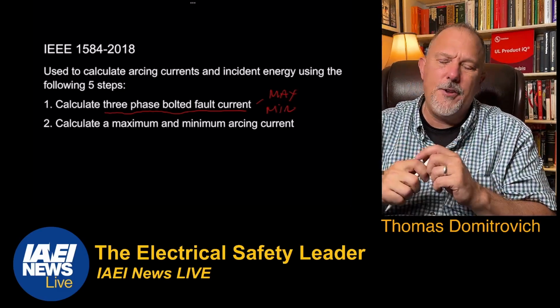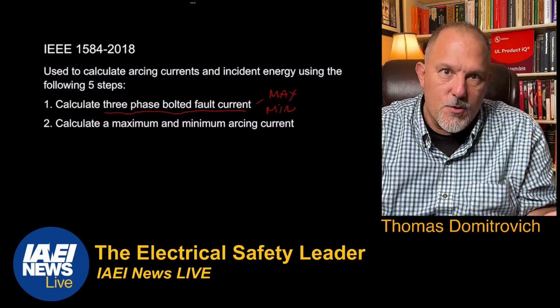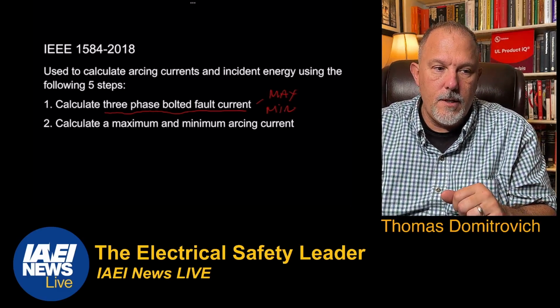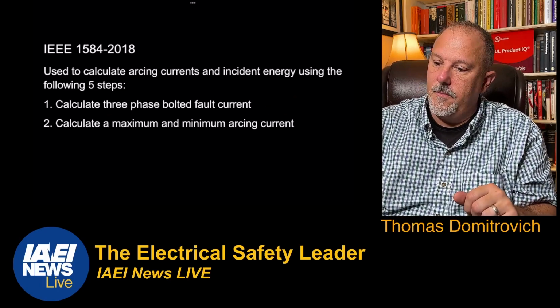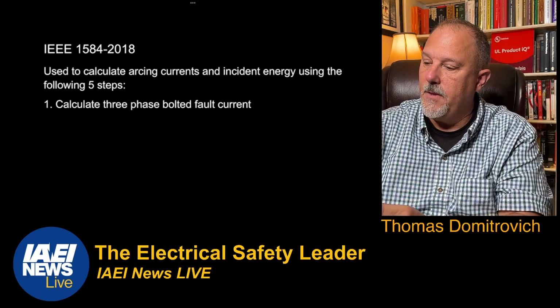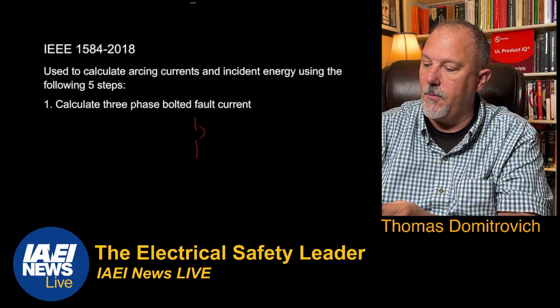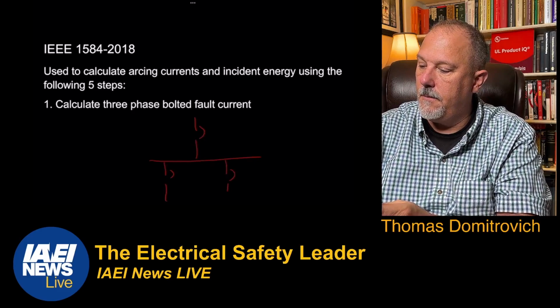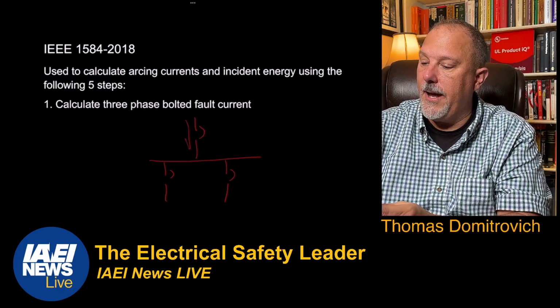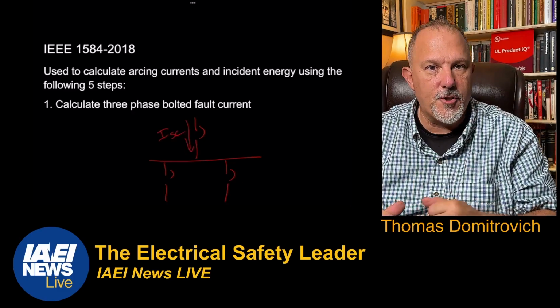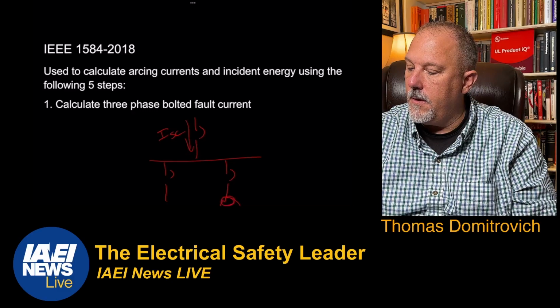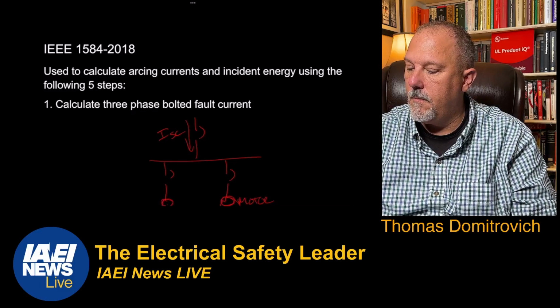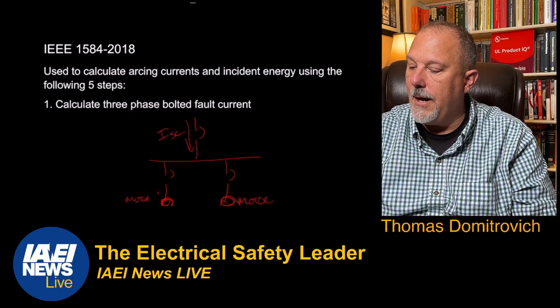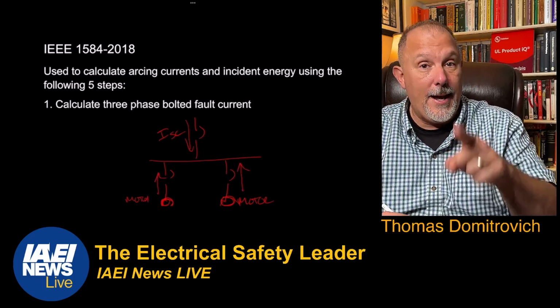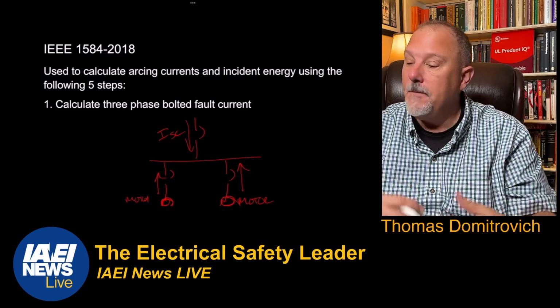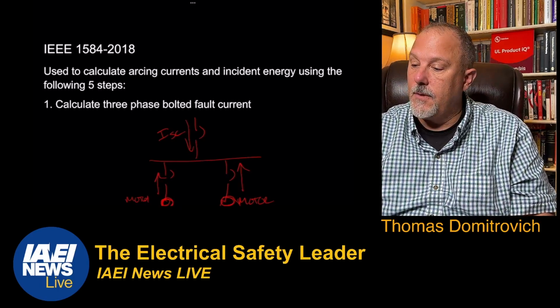So once I know my currents at every point in the system, I know my maximum and minimum short circuit values. And when you say, well, how do you calculate a minimum short circuit value? Here's one thought process. Let's go back to this. I'll give you an example. Let's say that I have a panel board like this, right? So I would have short circuit current coming from the upstream breaker. If these are motors, I'll also have motor contribution if those motors are running and if they're not on a variable frequency drive.